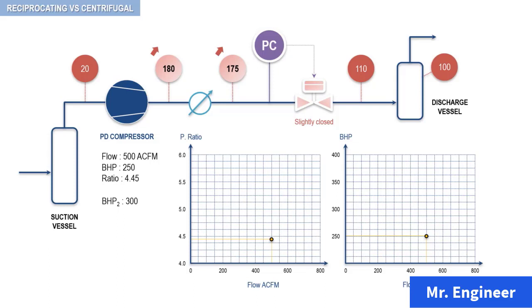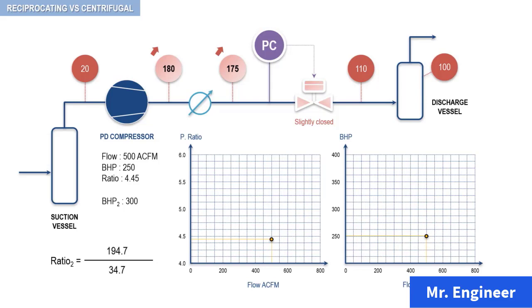First, we calculate the new pressure ratio. Recall, it is equal to the discharge pressure of the compressor divided by the suction pressure, and both pressures must be expressed in absolute pressure. So here, the new ratio is equal to 180 psi plus 14.7, divided by 20 psi — the suction of the compressor, which remains unchanged — plus 14.7 psi to convert it into absolute pressure.